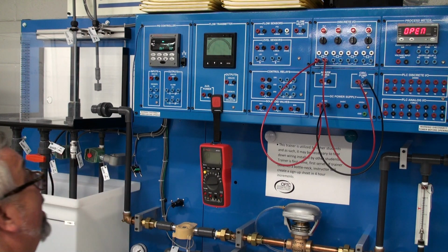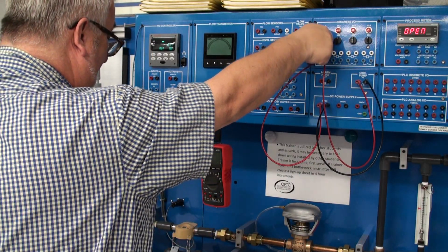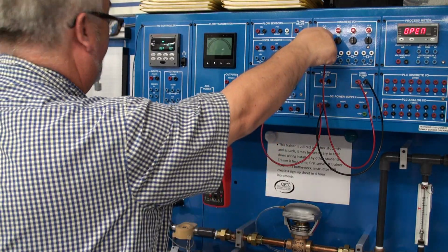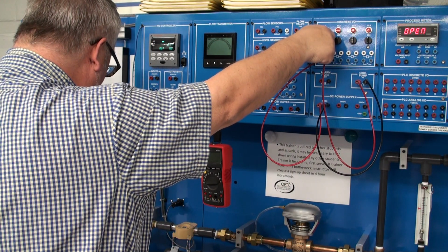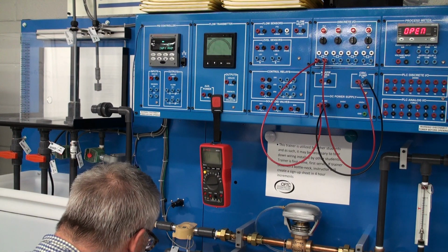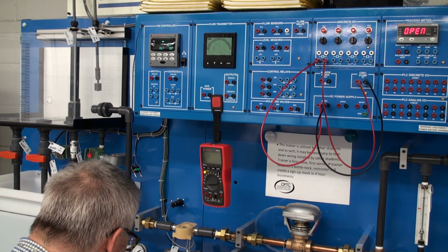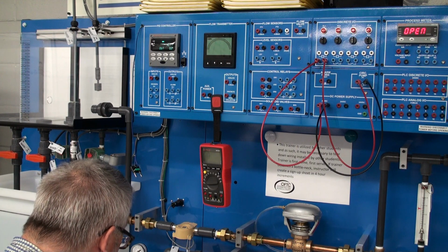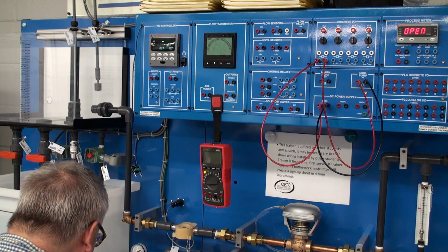Now it asks us to turn SS1 on, and when I do that, you should hear the pump, but we're not going to have any flow. I don't know how well you can hear that, but I can hear the hum of the pump now. And you can actually see the pressure on the pump rising, and I'm not going to run it long because we're not moving water, and I don't want to damage that pump. But it says even though the pump is now running, there's no flow because we've got the manual flow control valve, which is FV100, closed. So these are our manual control valves here. This is on that same sheet.